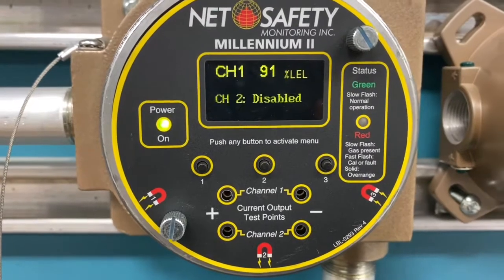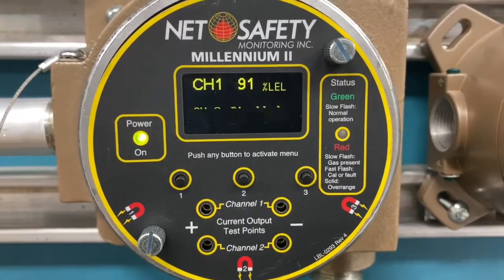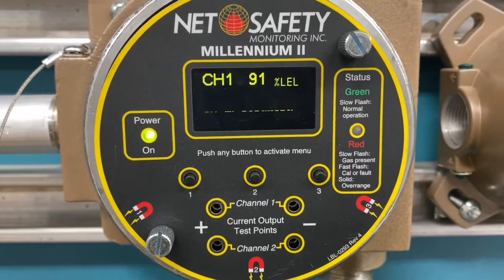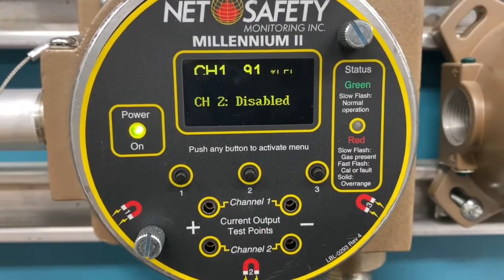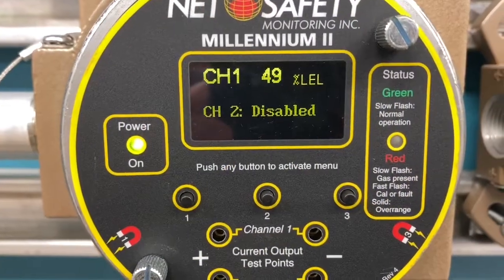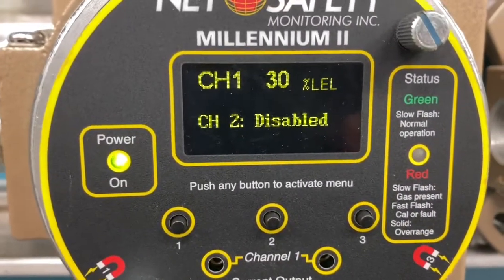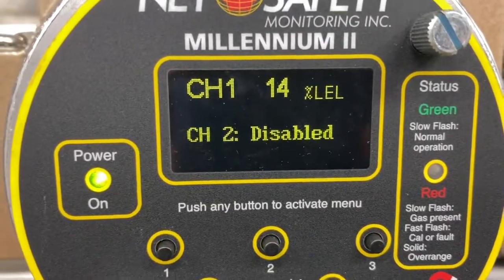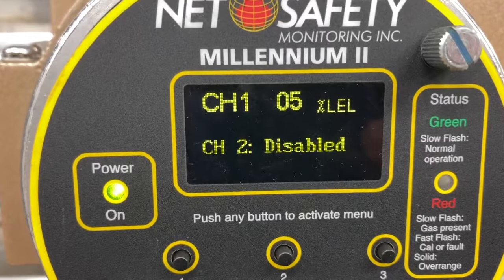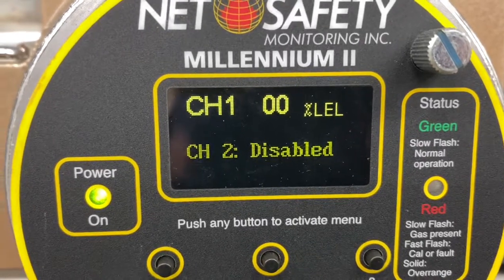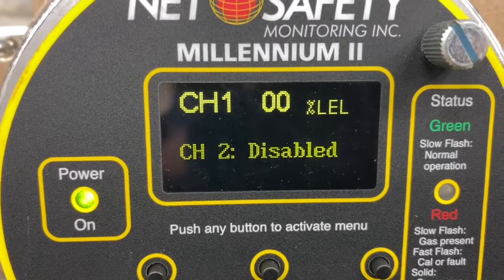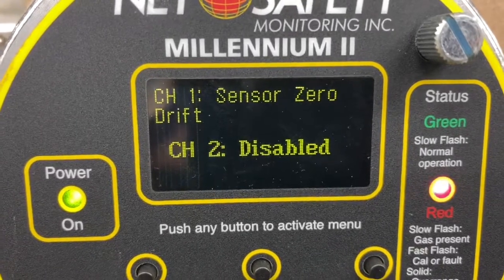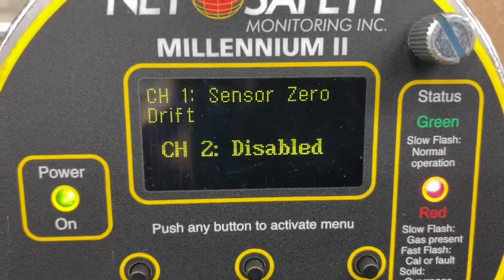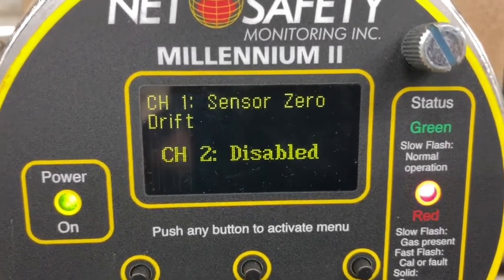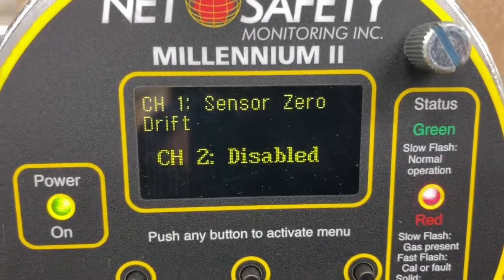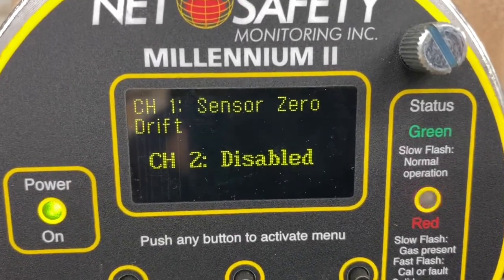I'm going to go and throw the zero gas on it one more time, just to have a peek, just to see if that gets rid of our zero error. But we'll see here, and I'll apply the zero gas and see what it does. The air again, and it's dropping down, you can see, and we'll just see what it does once it hits close to 0. Oh, there, so it went back into sensor zero drift. So it must be, the range must have really expanded above and below the limits, or the calibration values, sorry.